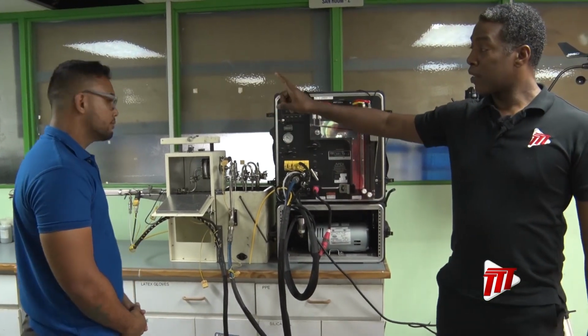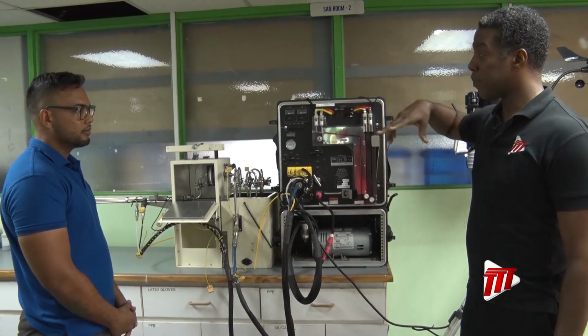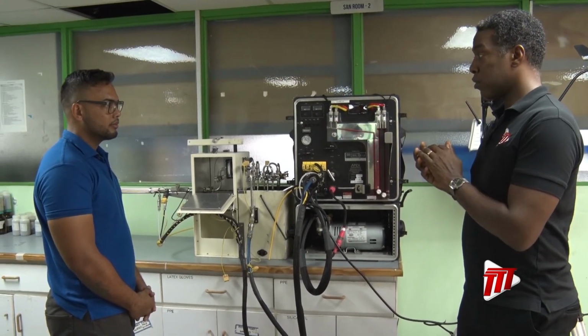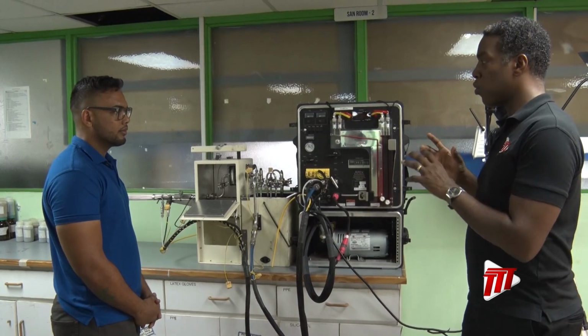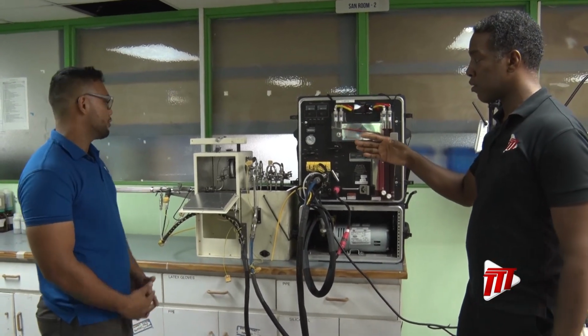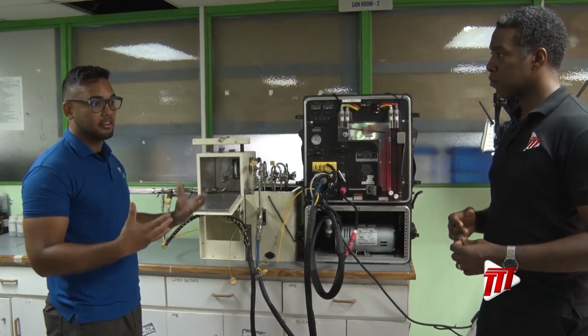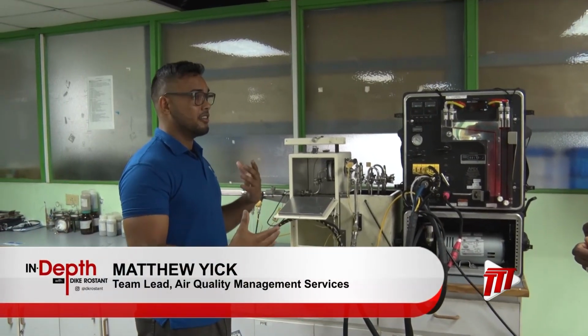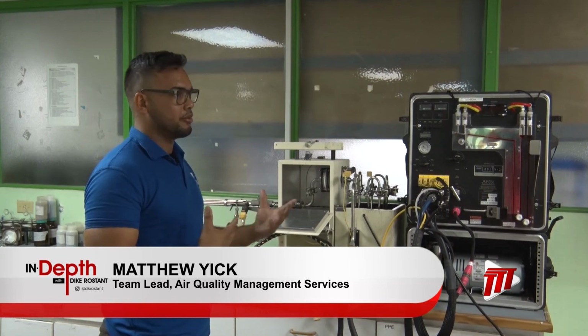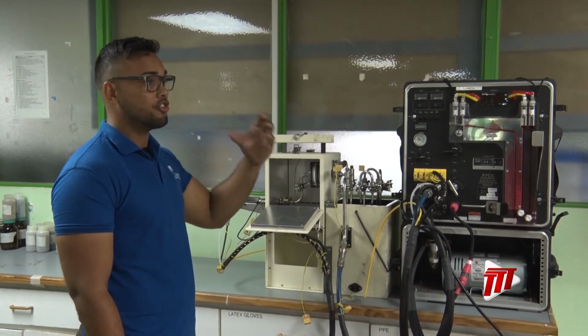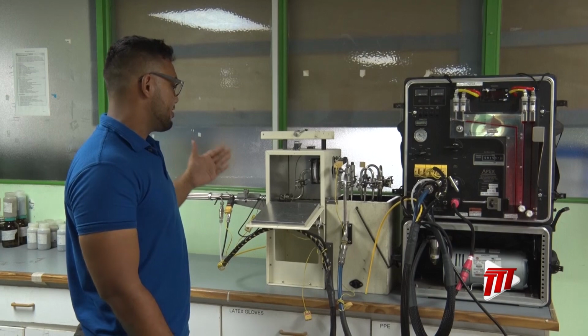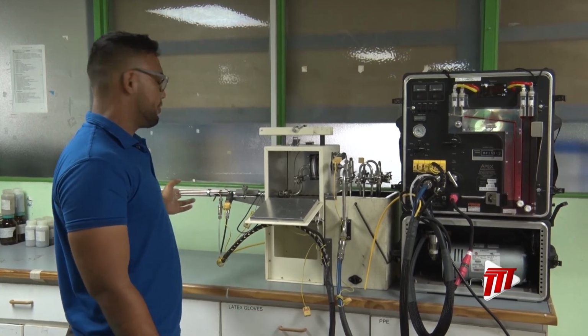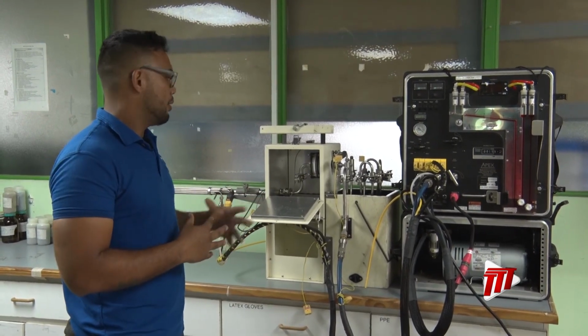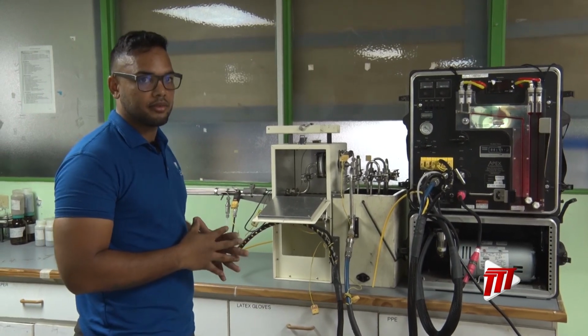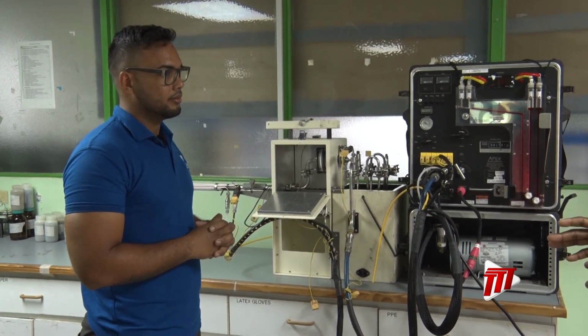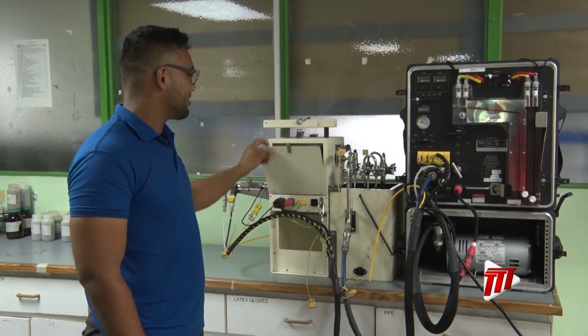And so I take it that stacks are built with apertures or places that can be opened so that the probe can be inserted. Correct. Most stacks would have ports. If your stack doesn't have a port, we would usually facilitate a free site visit where we come and do some measurements and calculations and tell you exactly where it should be. Depending on the size of the stack, we have different probes. This is a 3-foot probe for a fairly small stack, but this could go all the way up to 20 feet. Something else to carry up this time. Yes, something else, something very heavy.